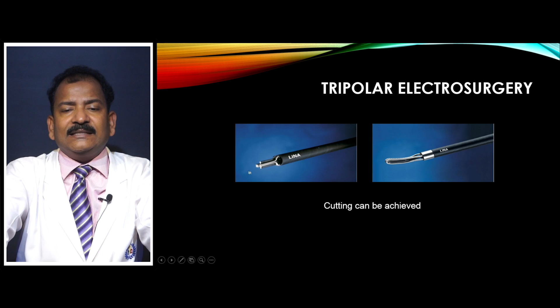So, what you need to do is coagulate, and you do not have to bring the scissors. We know that bipolar does not cut. So, you have to coagulate with the bipolar and cut with the scissors, but in tripolar you do not have to bring them, because it has an inbuilt knife, and after coagulating you will press it, a knife will come and it will cut. That is why it is called tripolar, but there is nothing like a third pole in the world. Basically it is a bipolar with a cutting blade.